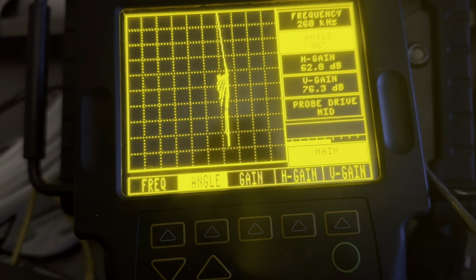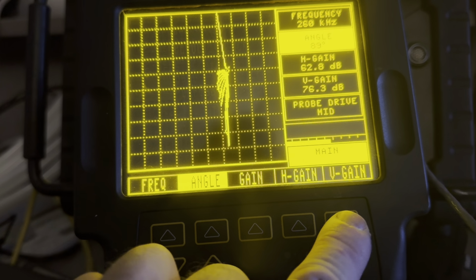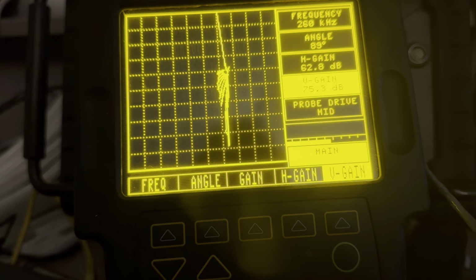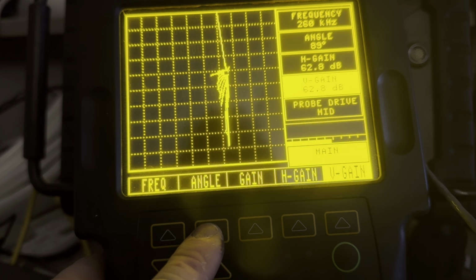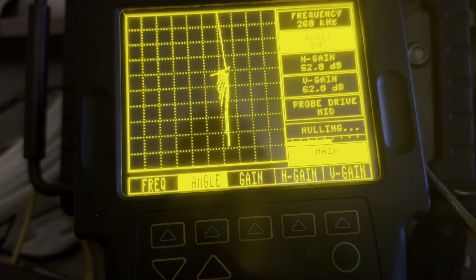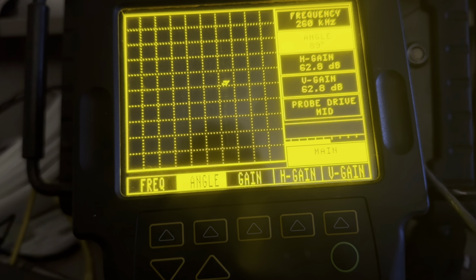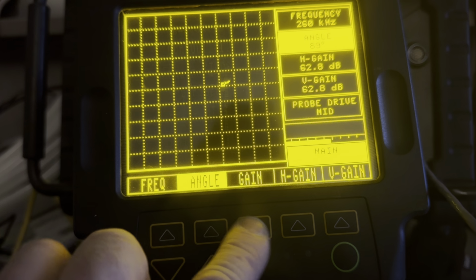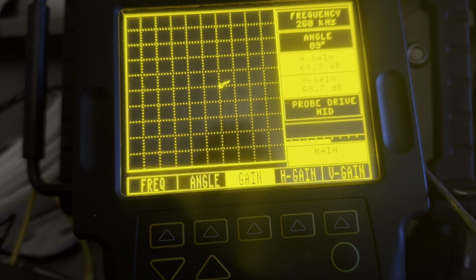Now keep in mind, I have manipulated the vertical gain. So that could sort of mislead us that something's wrong with our probe or cable, where it may have just been that I forgot to adjust my horizontal and vertical gains to be the same. That's important, so it doesn't screw up your aspect ratio. Okay, so now I'm nulling with my weld probe, and I'm erasing, and I'm getting a little blip there, but I don't have enough gain. So now let's crank up both of the gains simultaneously.